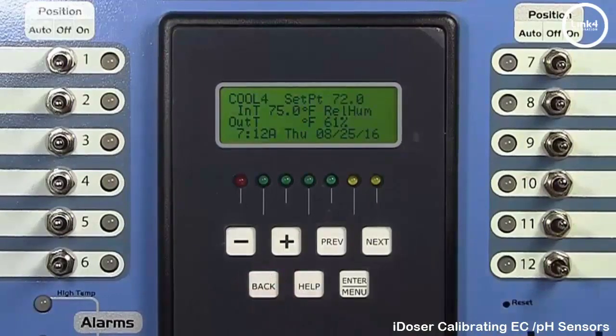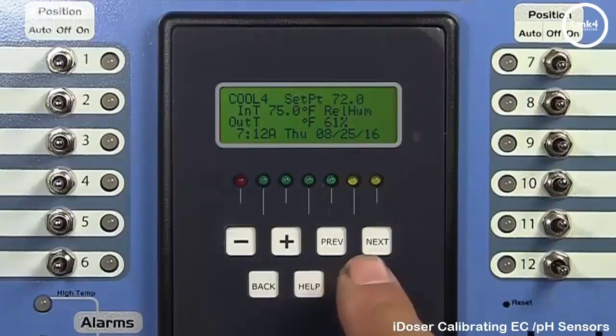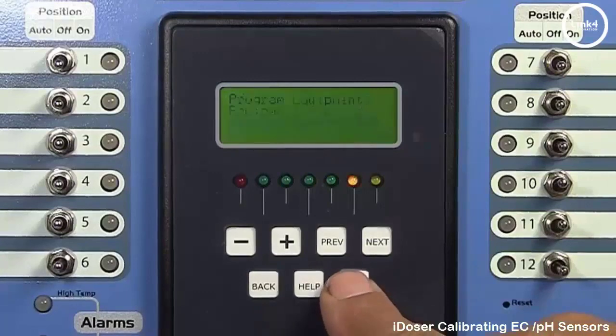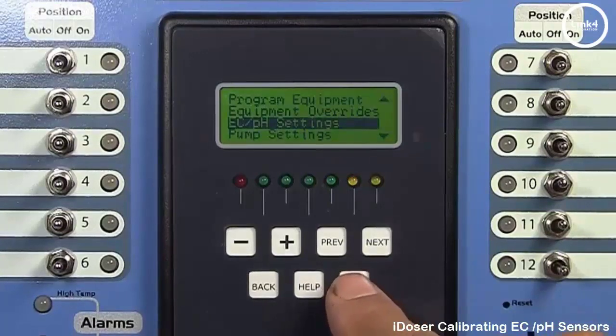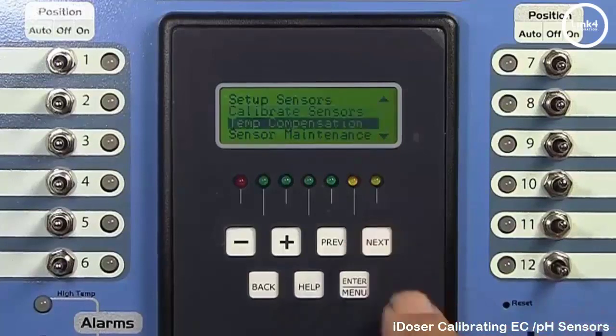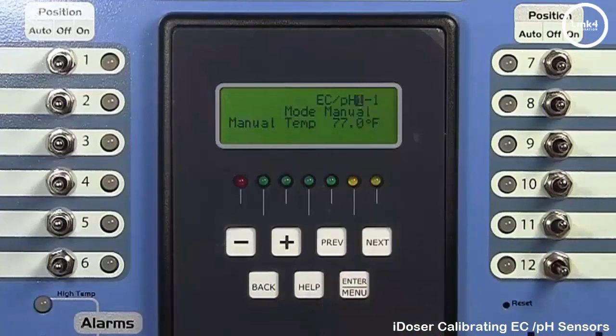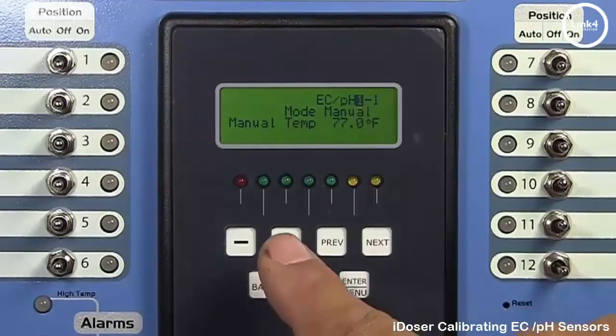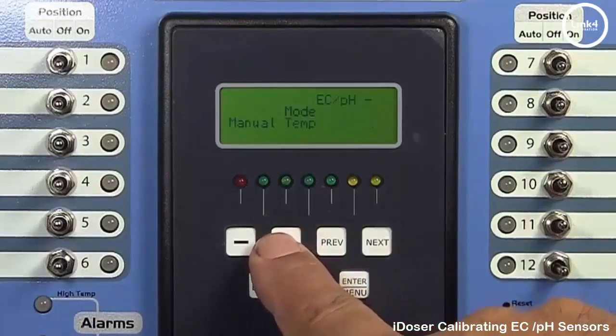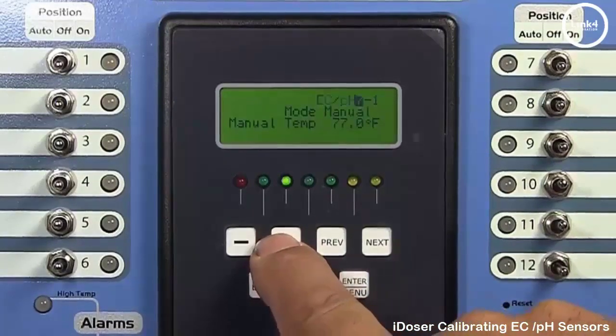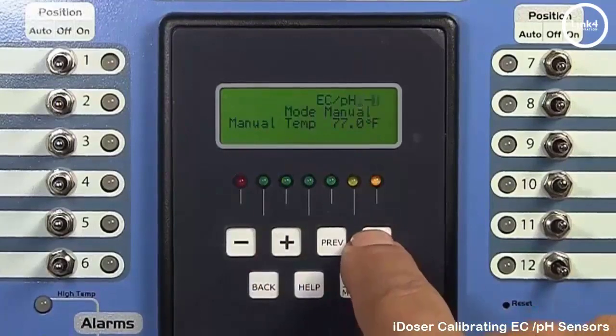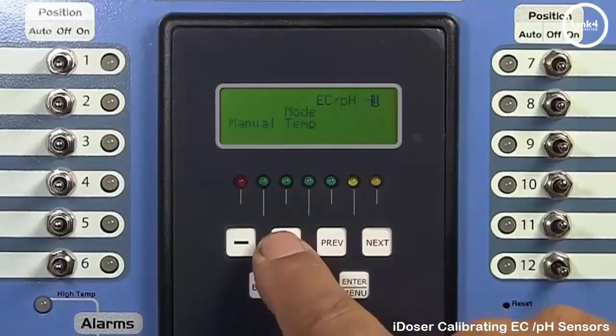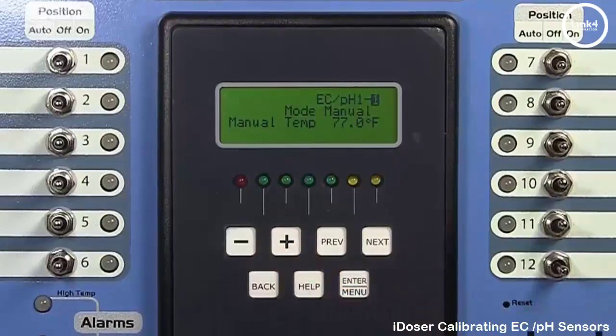And finally, temperature compensation for the temp sensor in the EC probe. Now to do this, we're going to hit Enter Menu, iDoser Programming, ECPH Settings, and we'll go ahead and highlight Temp Compensation, hit Enter Menu. Now with Temp Compensation, it gives you the option to change between tanks as well as change between transmitter boards. And for this example, we will be using tank 1, transmitter board 1. Hit next.